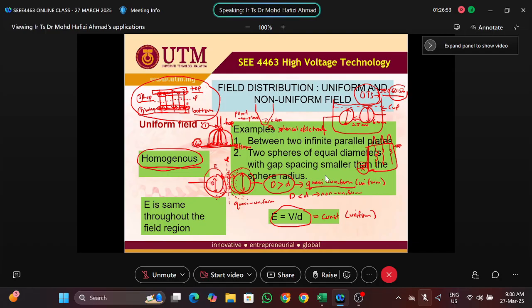We apply a voltage on these ball electrodes, and then the breakdown may happen. We take the breakdown voltage value, and the breakdown voltage should be more than or equal to 30 kV. This is for medium voltage level. For high voltage level and extra high voltage level, the breakdown voltage should exceed 35 kV. If I'm not mistaken, this is according to IEC 60422, which mentions the acceptance limit for the breakdown voltage of this transformer oil.